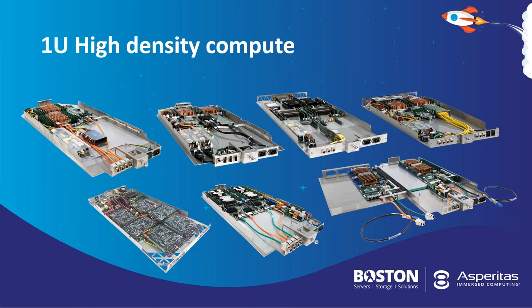The way we achieve this is by compressing the IT into a 1U space. So if we look at the type of server designs we developed together with Boston, we're looking at highly consolidated server designs. We can fit a lot more compute into a 1U space. We use specialized chassis for liquid, and we optimize the designs for liquid, which allows us to get to much higher densities, even though we're losing about half the three-dimensional space because we're using vertical position servers. We can still achieve much higher densities than anything else you can do with air.